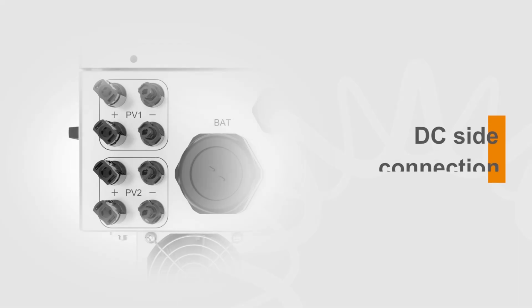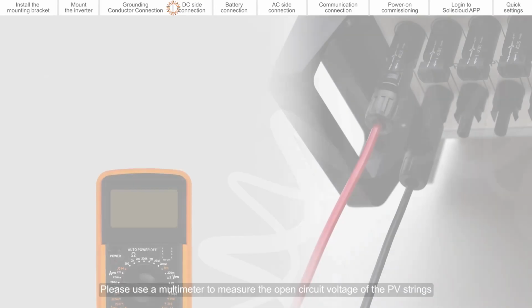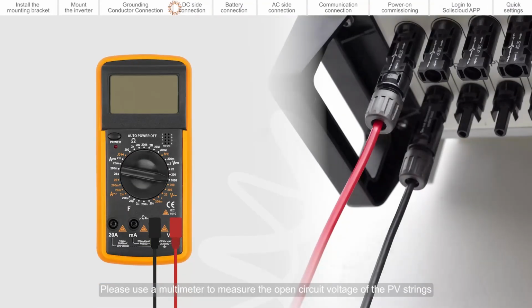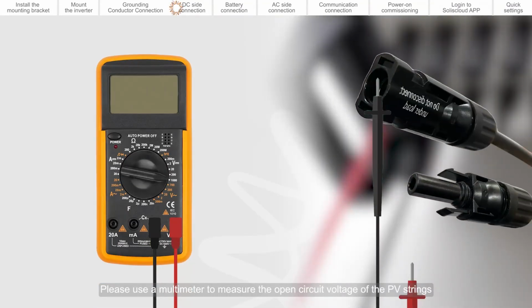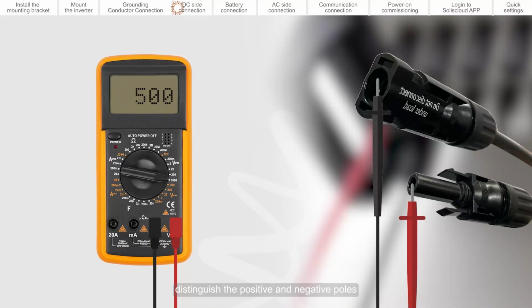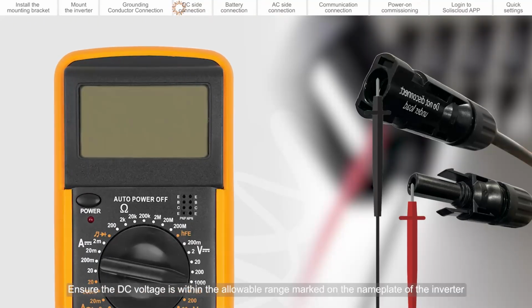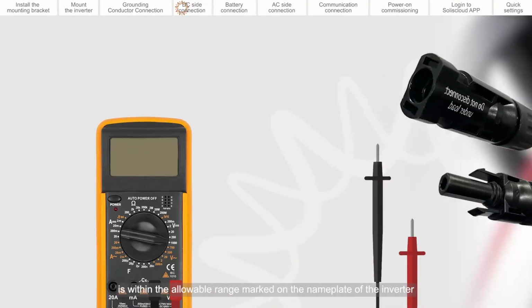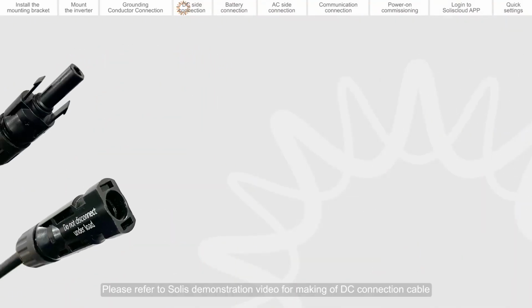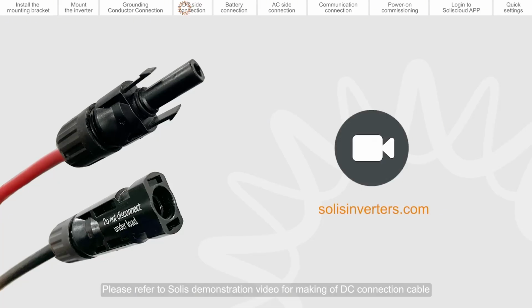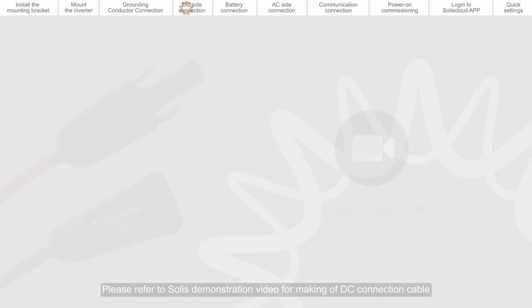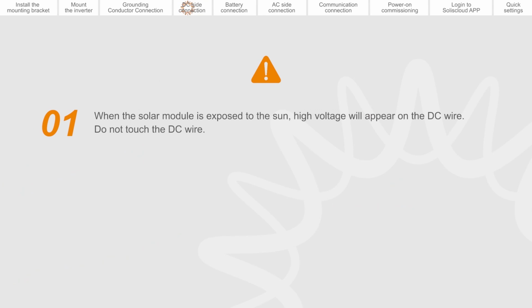DC side connection. Please use a multimeter to measure the open circuit voltage of the PV strings. Distinguish the positive and negative poles. Ensure the DC voltage is within the allowable range marked on the nameplate of the inverter. Please refer to Solis demonstration video for making of DC connection cable. When the solar module is exposed to the sun, high voltage will appear on the DC wire. Do not touch the DC wire.